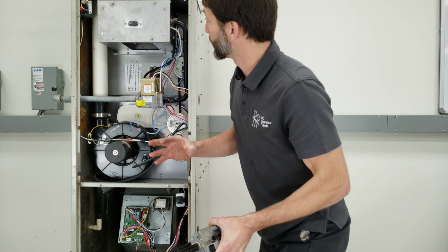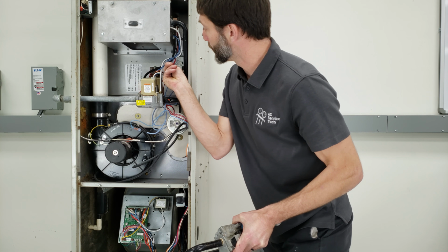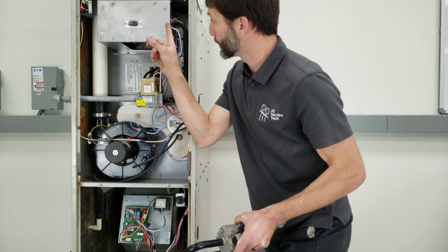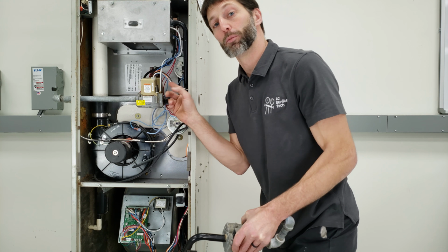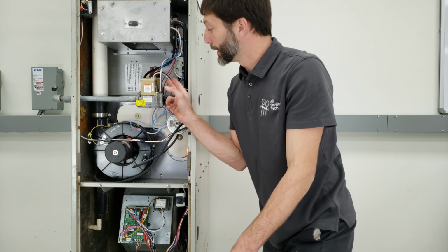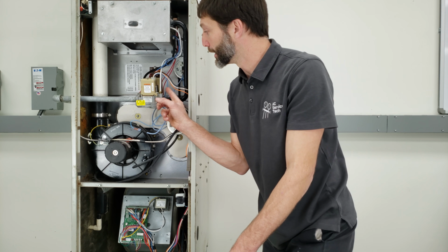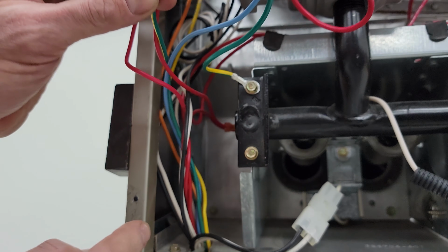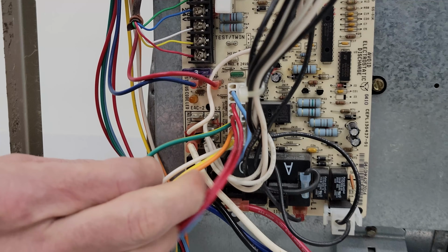But basically on this one, this section of wiring right here could be changed out for your smart valve from here over to here. And this little pilot tube, a lot of times with the pilot ignition, this is your ground. And so you got to make sure that this is snug and tight and not corroded. On other furnaces, you want to make sure that you have a good ground wire from your combustion box down to your control board.